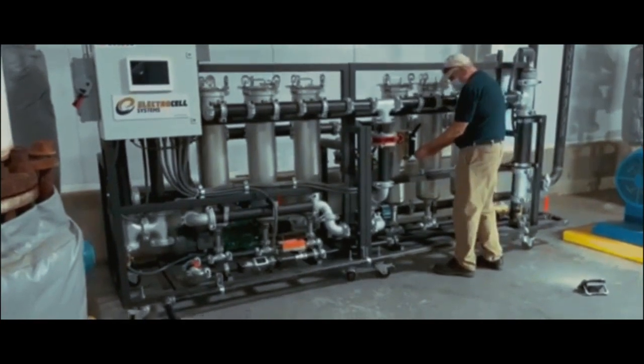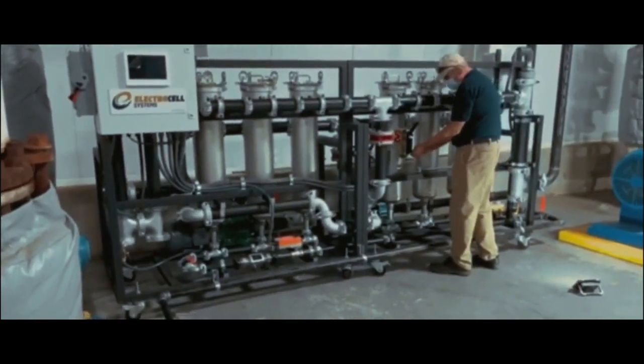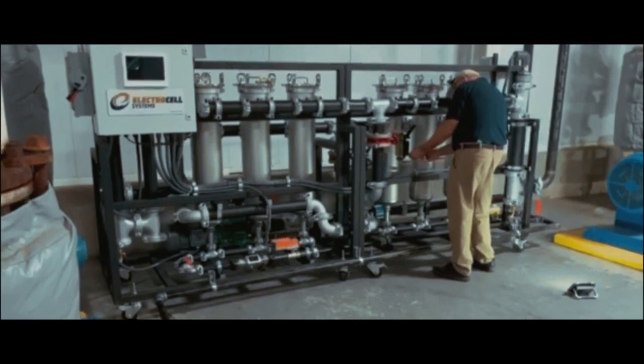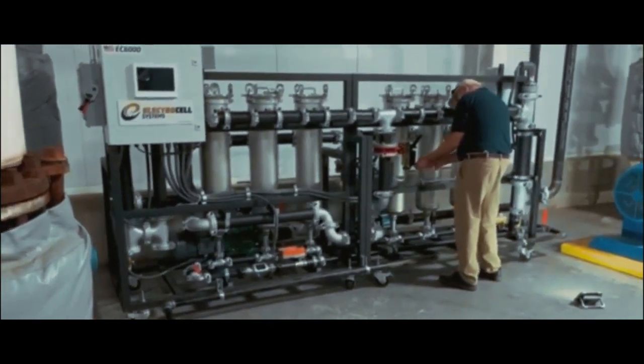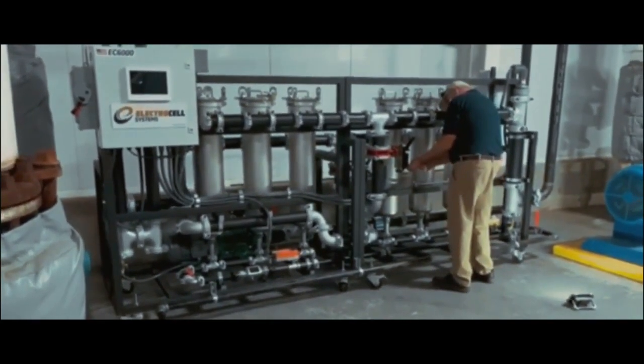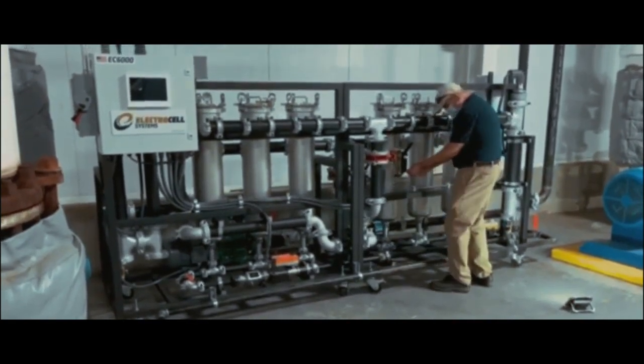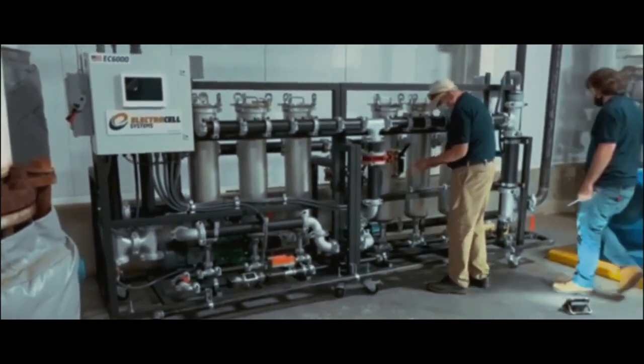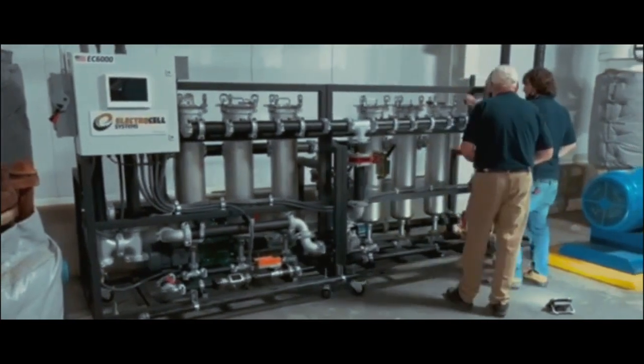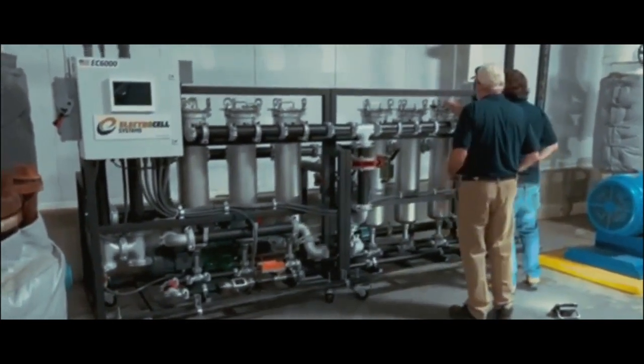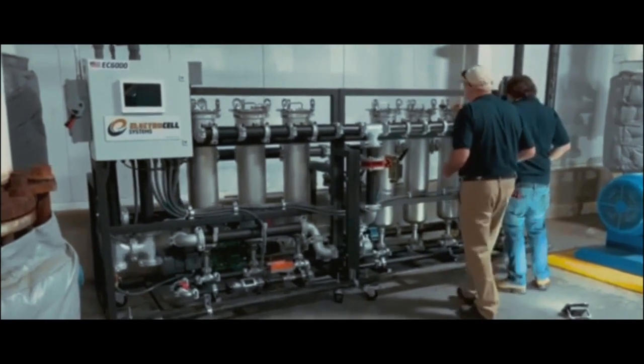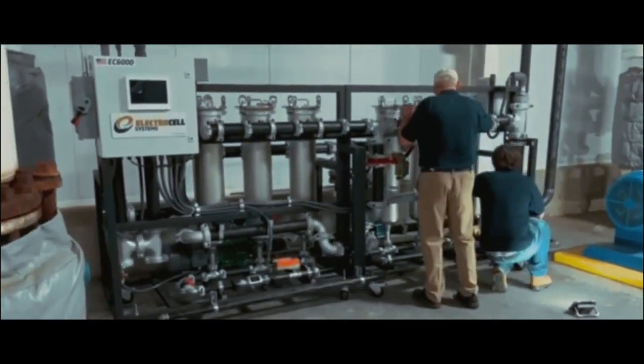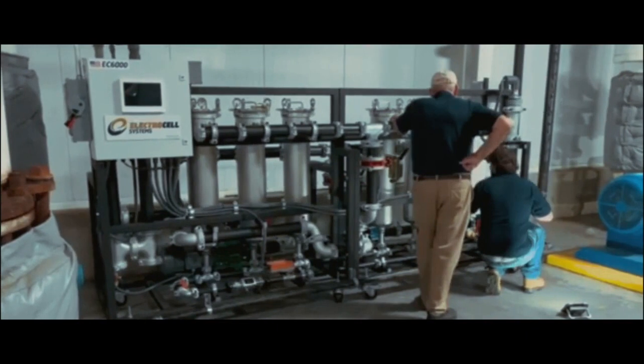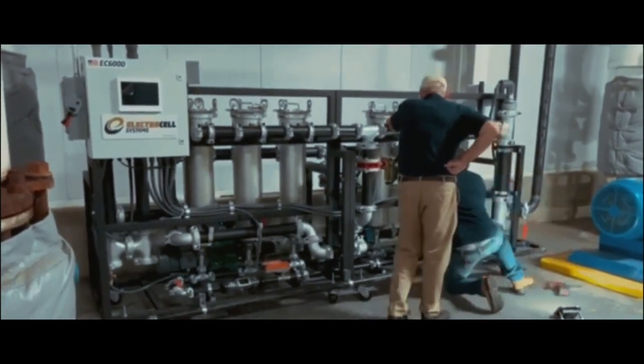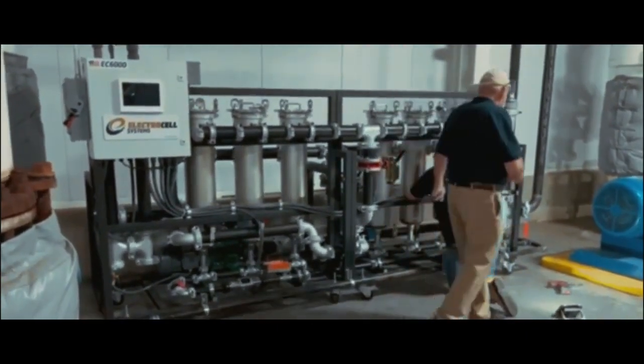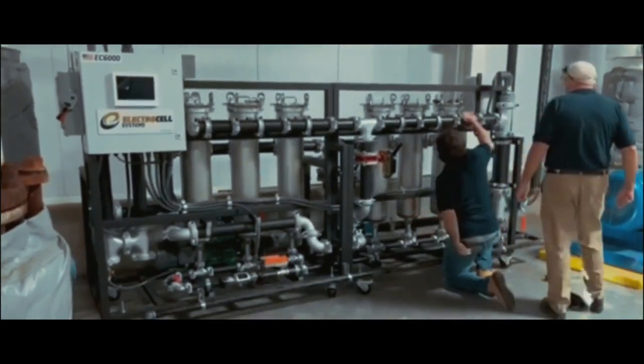Both of the EC6000 systems have been pre-installed prior to ElectroCell's arrival in Canton. The first step in the startup process is to carefully inspect the equipment to assure that there was no damage during shipment. The systems are then inspected for leaks, electrical input voltage and amperage are checked, pump rotation and direction are tested, water flow is balanced to assure optimal gallons per minute, and conductivity set points are checked and established. Finally, all of these items and more are recorded on the startup check sheet.